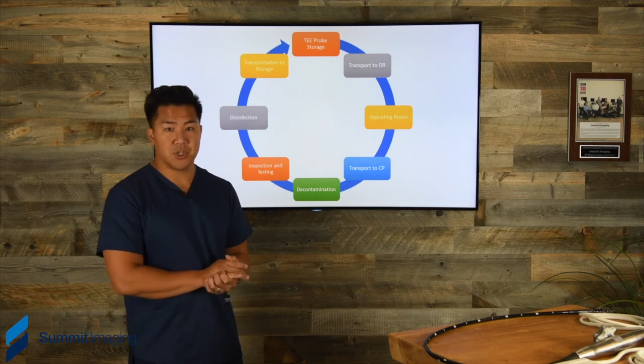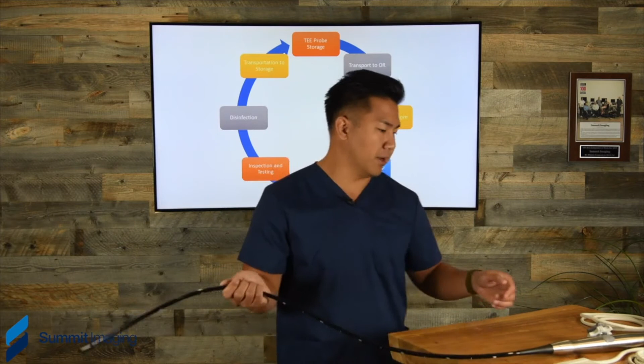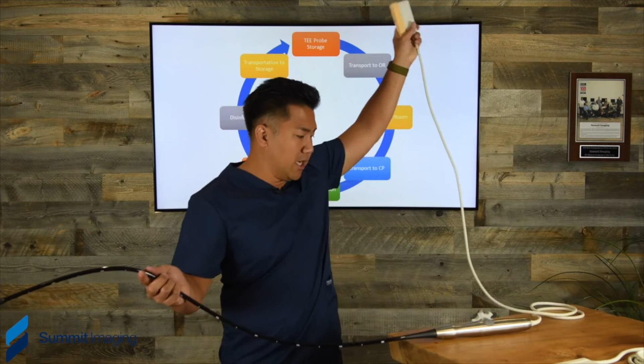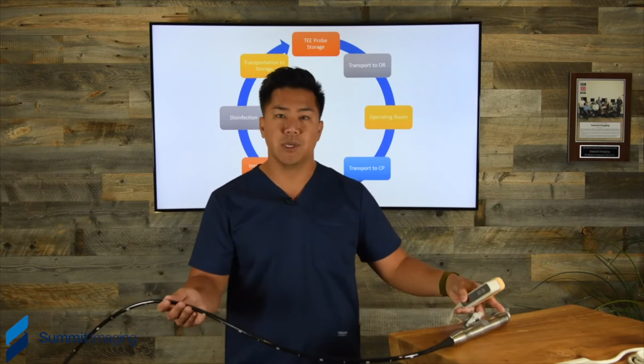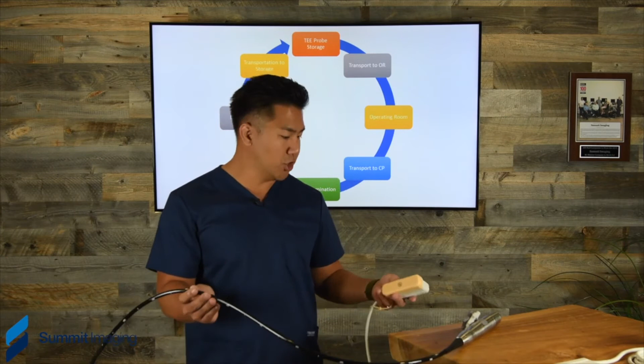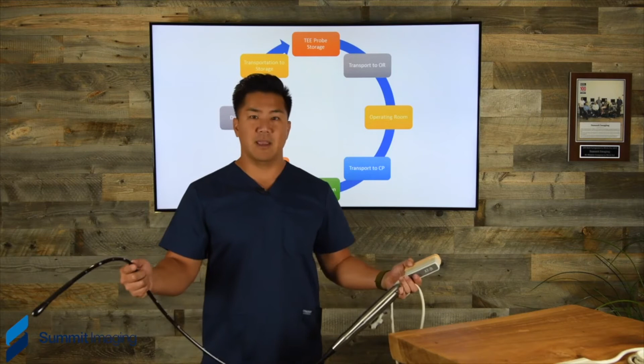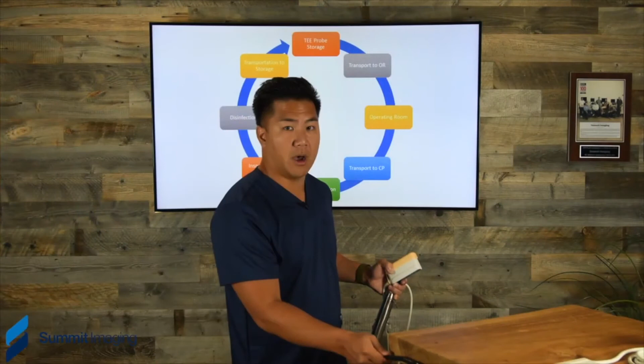And at transport, there's a couple of vulnerabilities here that we often see where damage occurs on probes. And let's just start with the obvious TEE probe, because these are actually damaged quite often when they're being transported. Now, when we're in hospitals helping assess these kinds of problems or deploying our evaluations to show the hospital what they could do differently to help prevent damage, this probe is so long that it has a lot of force if it's swung around. And the part you want to protect the most is the tip. There are so many microelectronics in here with a very sensitive crystal that even the slightest bang on a surface will crack it enough to where the probe needs to be repaired or may need to be completely replaced.